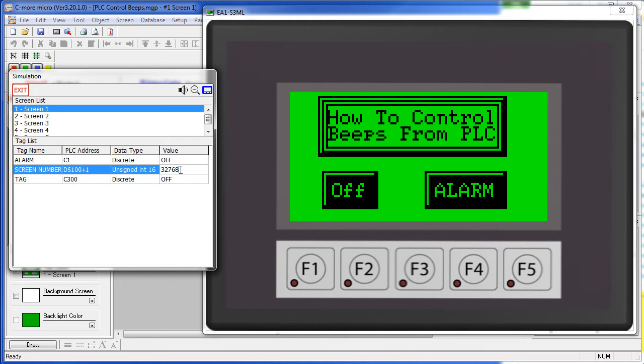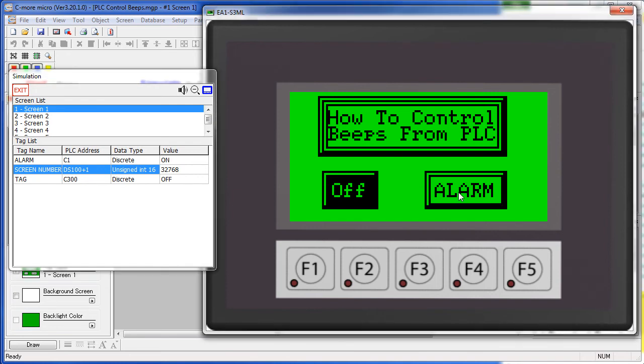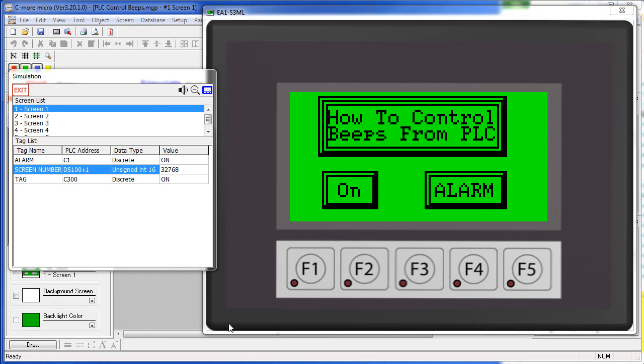By setting this bit, the PLC is telling a C-more Micro it's OK to let the user silence the alarm by touching an object on the panel or by touching a function key. Let's try that real quick. So bit 16 is set – we are going to start an alarm – so now I can silence that alarm by hitting a function key or by hitting an object on the screen. That's a real handy feature to have and your users will thank you for that.